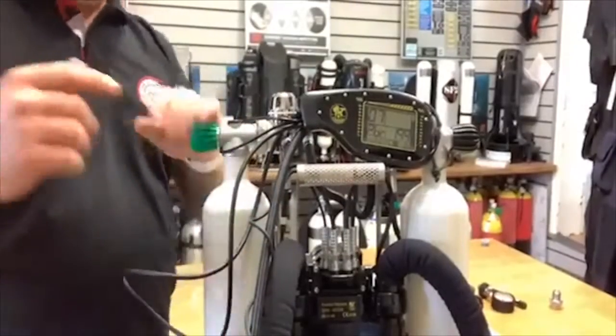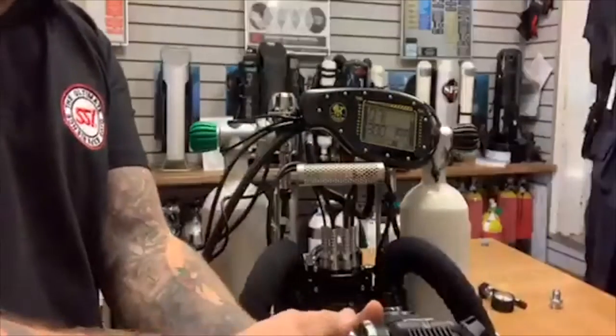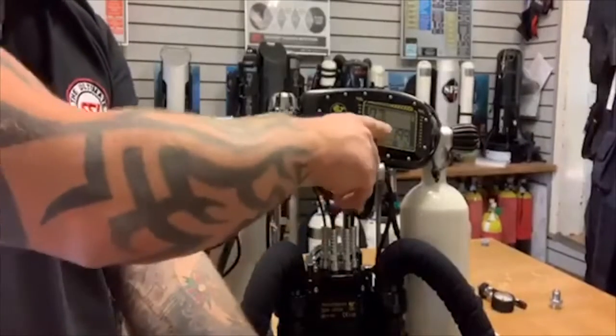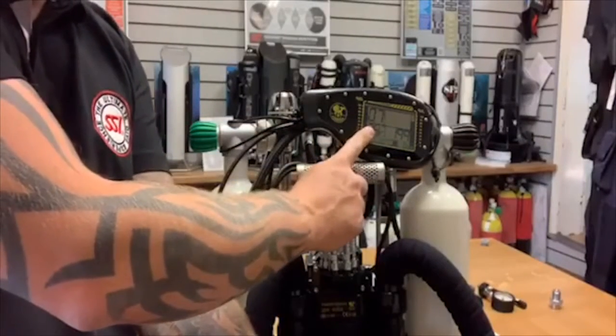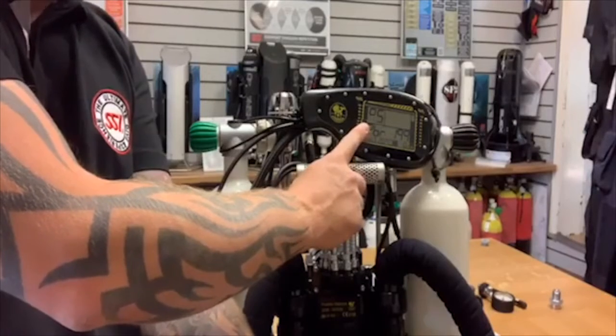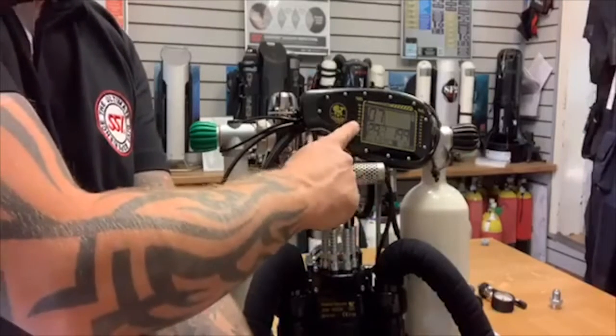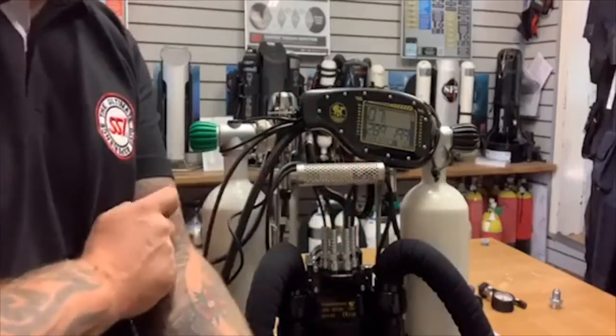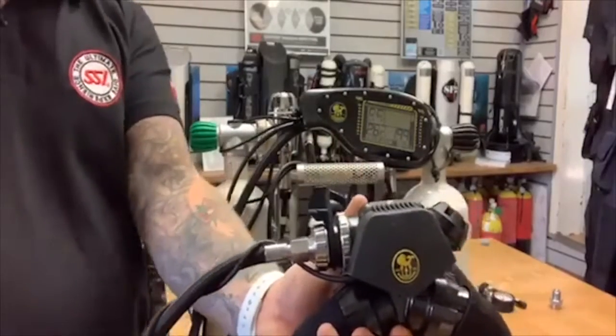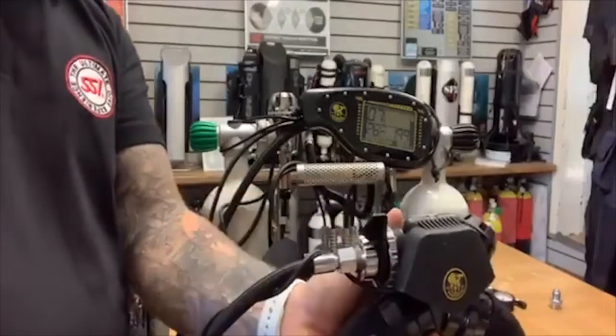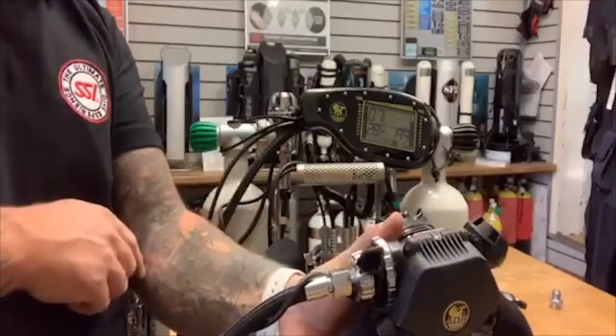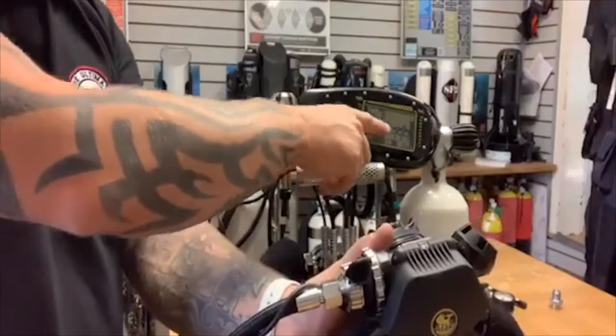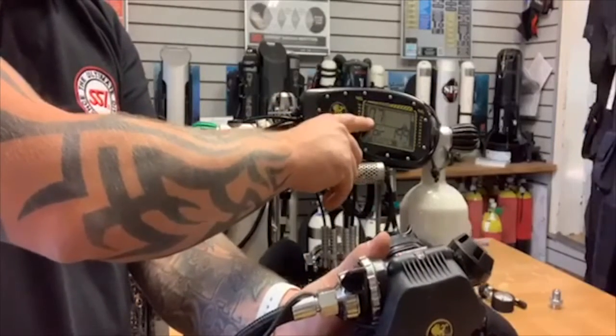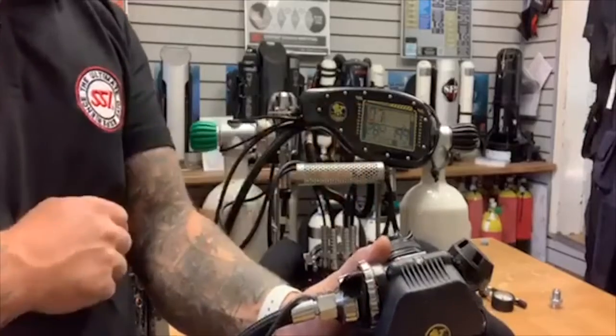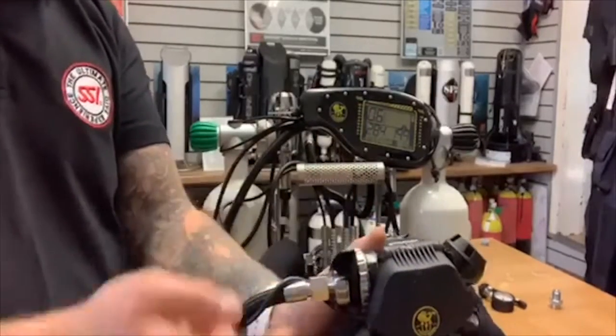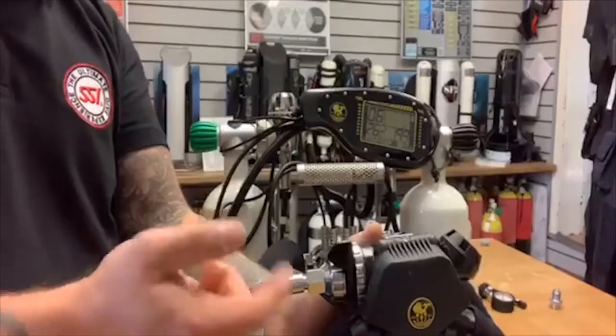Okay? If I move the mouthpiece into the closed circuit position, what you'll see is that this now will change to CC. It's changed the set point to 0.5 because it thinks I'm going to go diving. And you hear it inject gas. And I've got CC now, so I'm in closed circuit. Okay, that's really fantastic because I know which position I'm in. If I was to go into the middle here and not really in any position, you can see that my HUD just lit up and I got a vibration, and now I've got an alarm, and it says on the handset, NC, no circuit. So that means I'm not in closed circuit, I'm not in open circuit, I'm in the wrong position. So I know that I'm getting an alarm.